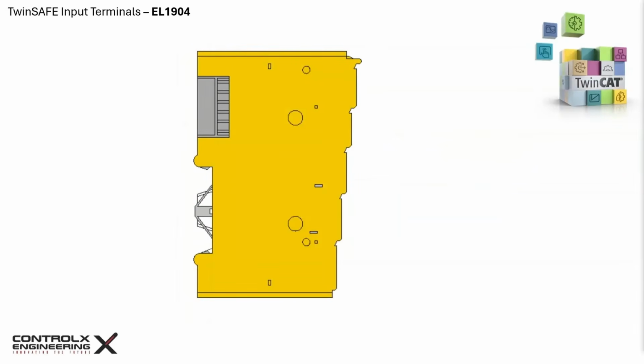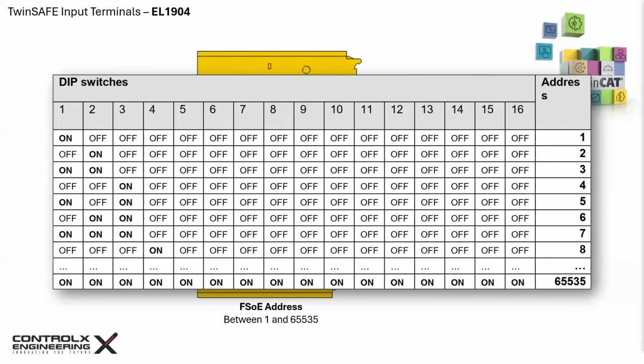On the EL1904, the TwinSAFE address is set using the 2 8-position dip switch blocks on the side of the terminal. Together, these switches define the terminal's unique FSoE address, which the logic controller uses to identify the device during safe communication. Because the address is set in hardware and not software, it provides a tamper-resistant identity that stays with the terminal, even if it is moved, replaced, or the project is reloaded. Each switch position represents a binary value, and by combining 2 8-bit blocks, you can assign a wide range of valid FSoE addresses between 1 and 65,535, to ensure every safety device on the network is uniquely and securely identified. This table shows the switch positions and the corresponding FSoE address.